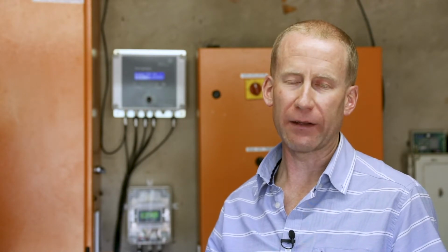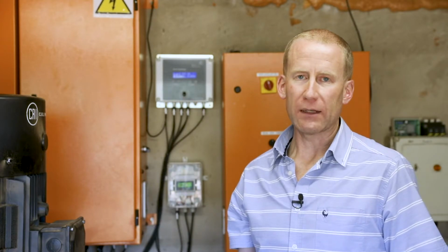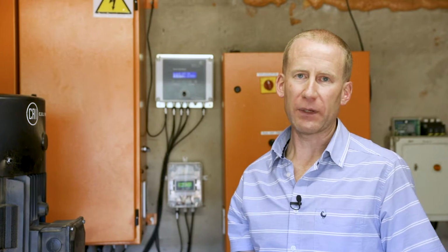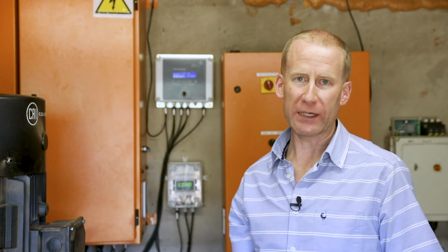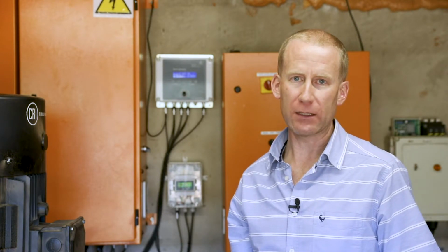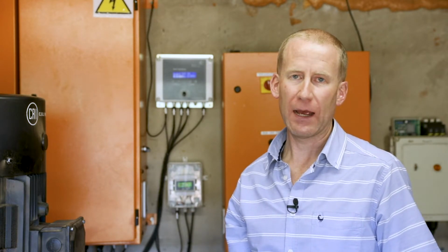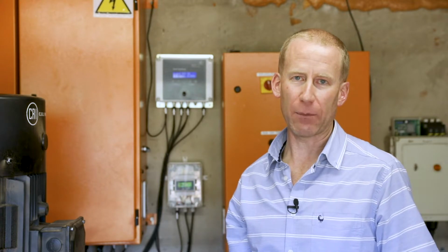In most cases, by selecting the correct pump and motor for a particular flow rate, we can achieve a dramatic saving in the kVA demand on the transformer. We can also optimize the combination of flow rate and pumping hours. This means that we might pump for a slightly longer period of time at a lower flow rate, but overall this allows more pumps to be run at the same time, and so we can achieve a higher application of water.